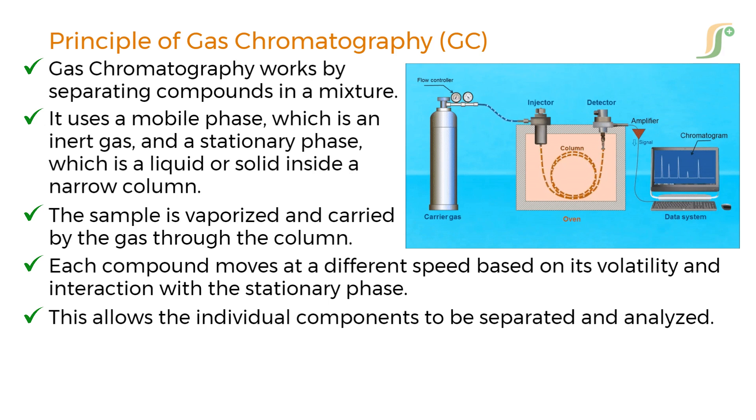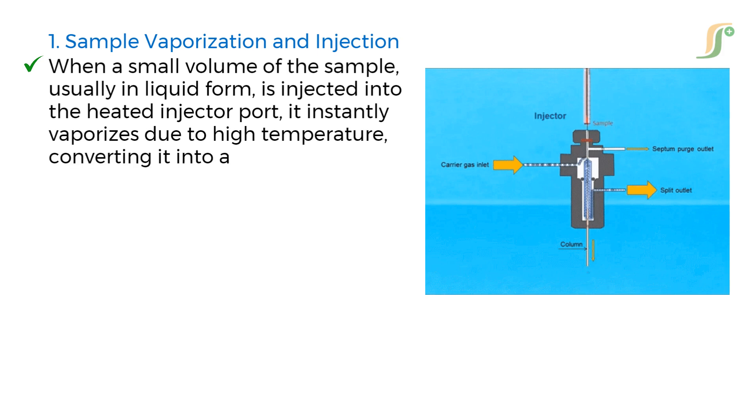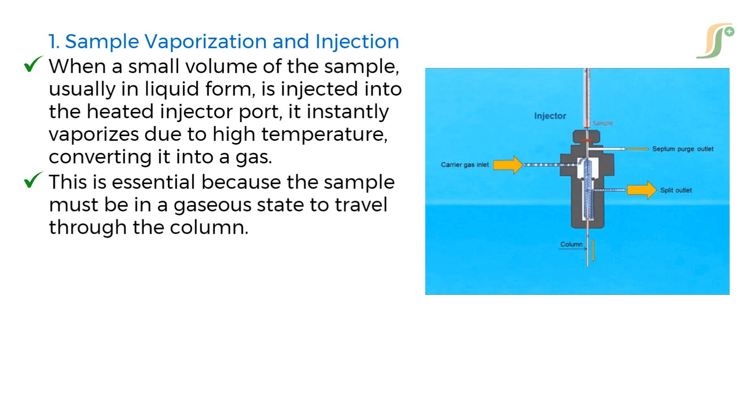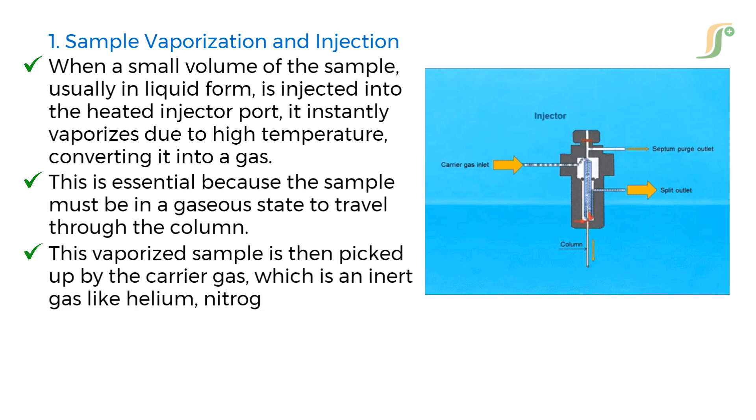Here's how it works step by step. Sample vaporization and injection. When a small volume of the sample, usually in liquid form, is injected into the heated injector port, it instantly vaporizes due to high temperature, converting it into a gas. This is essential because the sample must be in a gaseous state to travel through the column. This vaporized sample is then picked up by the carrier gas, which is an inert gas like helium, nitrogen, or hydrogen, and it acts as the mobile phase.